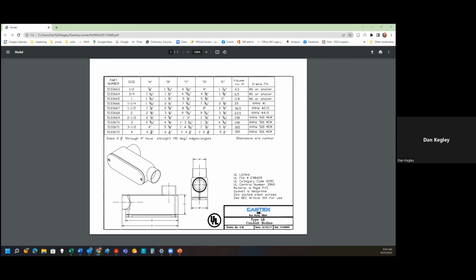location or not. If an engineer or somebody was to define that tank location as an explosion proof area, then you would have to use explosion proof fittings and boxes and those kinds of things. Gotcha. So they make an explosion proof NEMA rated box, which is basically, it's got, I don't know, there must be like 20 screws on the outside of the box, and it has to have conduit. Then you have to have seal offs to seal off the conduits with actual explosion proof putty and that kind of thing. Okay. But again, it draws back to who's designating that area as explosion proof or not. The NEC code doesn't define it.